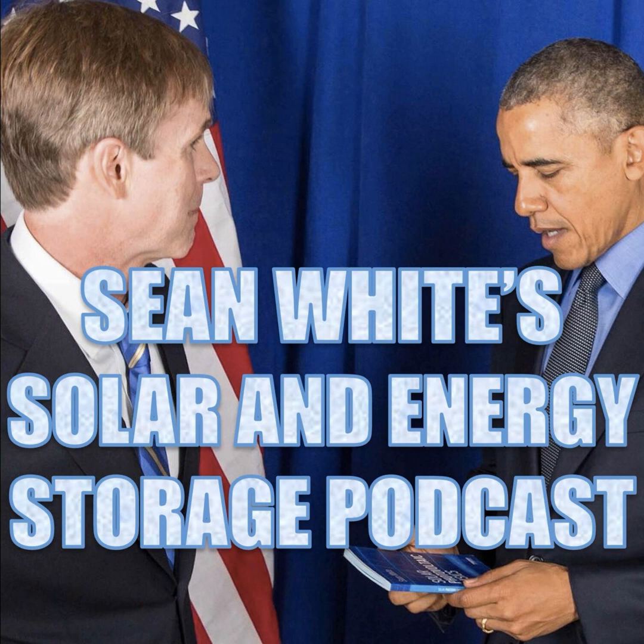Another thing about grounding and bonding is, just to be technical, grounding is connecting to ground, connecting to earth. In fact, in many countries, they call it earthing. So if you're in a different country, you might want to call it earthing instead of grounding. And then bonding means connecting everything together. So if you're connecting different pieces of equipment together, that means in case there's a loose wire, if that wire comes loose and touches a piece of equipment, and somebody touches that piece of equipment with their hands, they won't get shocked if everything's at the same voltage. So if everything is bonded together. So we bond together different pieces of equipment.